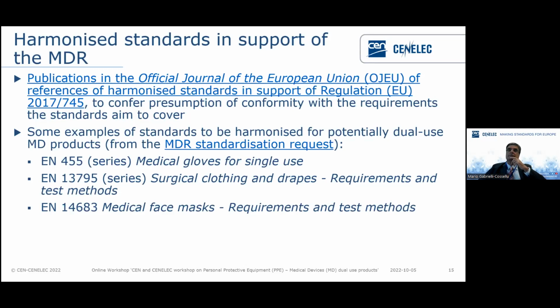Specifically, for example, a respirator must pass tests according to EN 149 and EN 14683, or using EN ISO 22610, and the legal requirements set out in the regulation 2016/425 for PPE and 2017/745 for medical device. A product certified as medical device must pass PPE certification as well if you have the dual function. Otherwise, dual use of the product cannot be allowed, and it cannot be claimed for dual use.